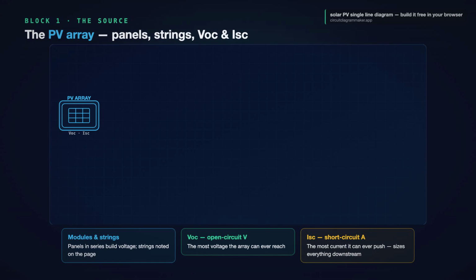And two numbers that matter more than any others here: VOC, the open circuit voltage, and ISC, the short circuit current. Why those two? Because every protection device and every cable downstream is sized against them. The maximum voltage the array can ever reach and the maximum current it can ever push. Get Voc and Isc on the page, and the rest of the drawing has something to size against.